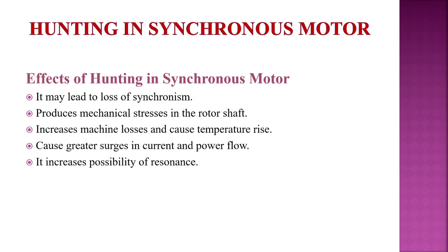Now let us see the effects of hunting. What can happen if there is hunting in a synchronous motor? First, it may lead to loss of synchronism. Second, it will produce mechanical stresses in the rotor shaft. Third, it increases the machine losses and will cause temperature rise. Fourth, it causes great surges in current and power flow. And fifth, it increases the possibility of resonance.